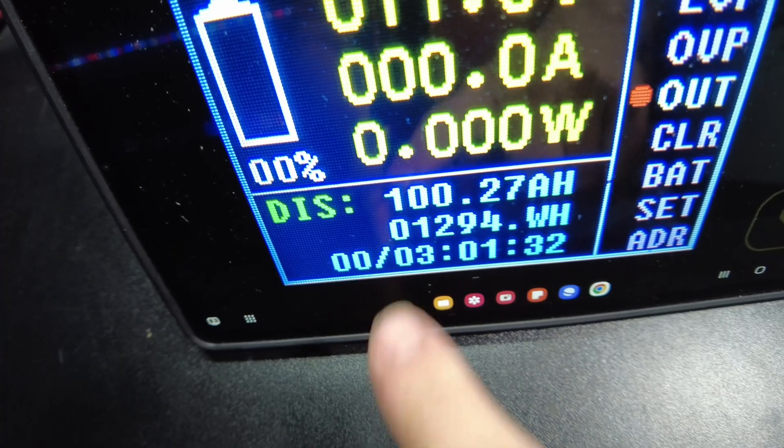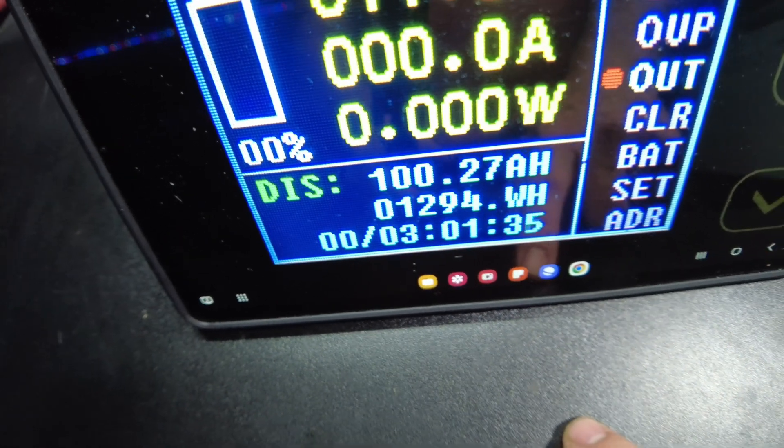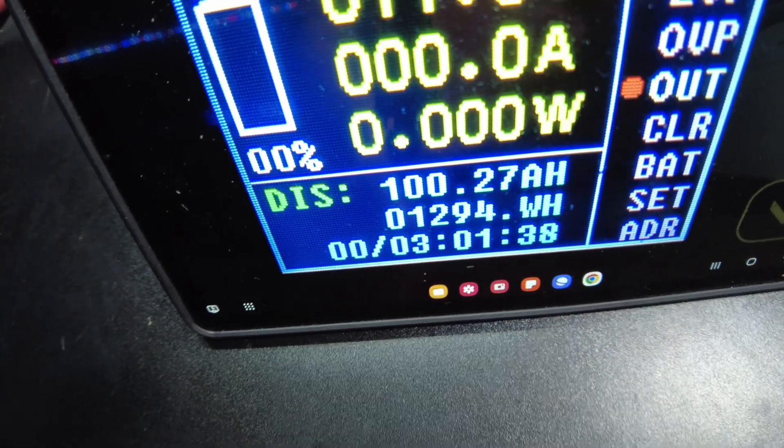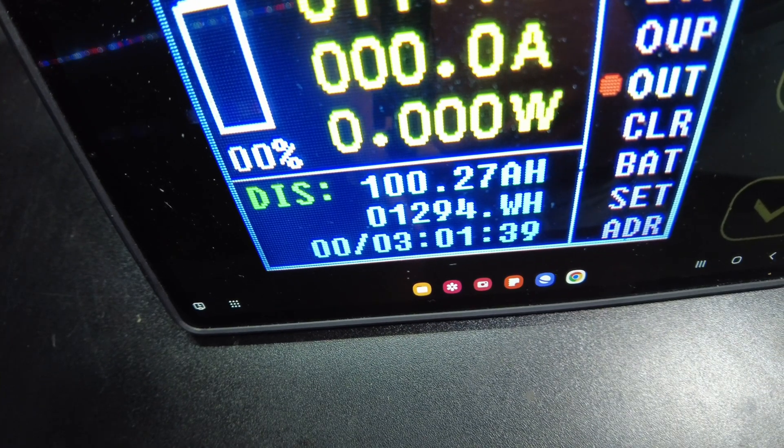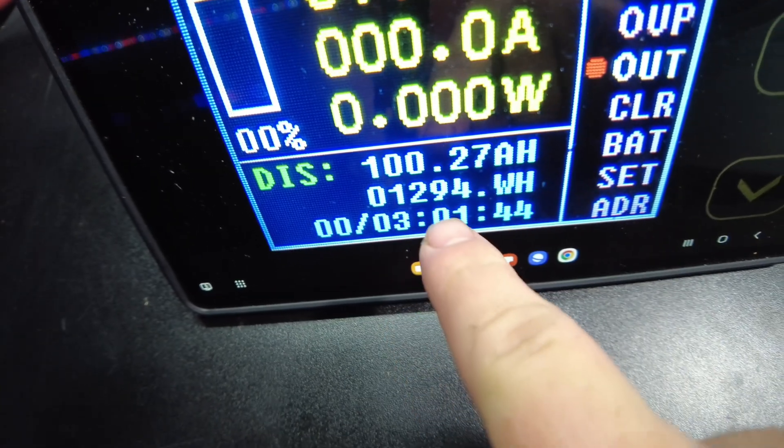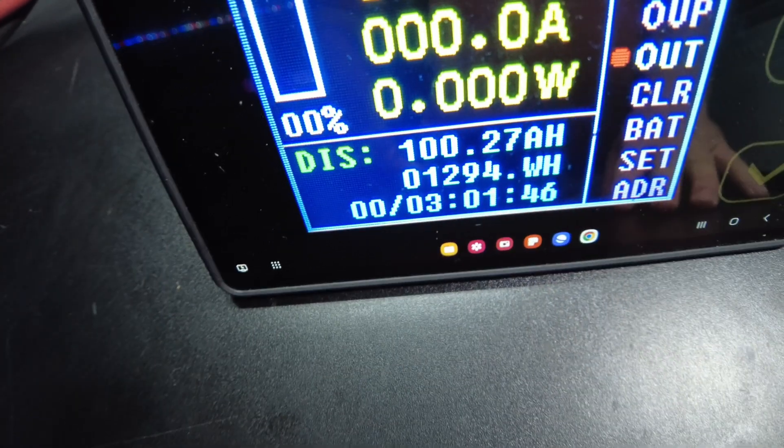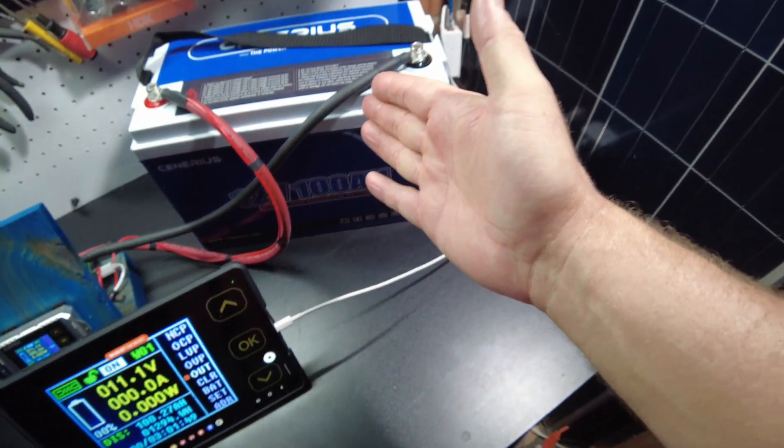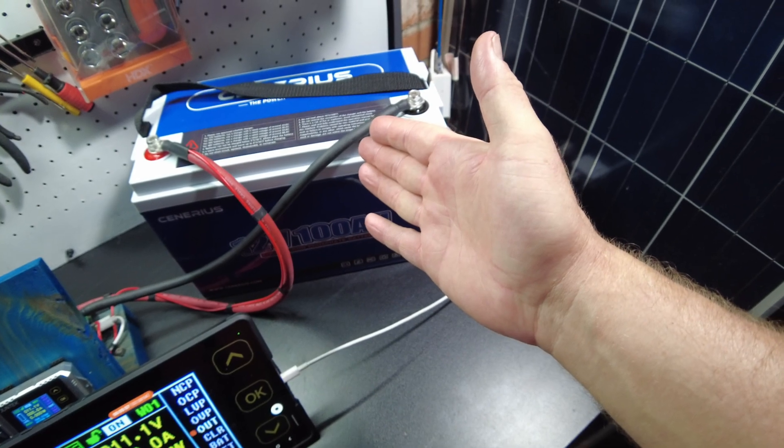So, that was close. We made it to 100.27 amp hours. 1,294 watt hours. So, we exceeded the amp hours and we did exceed the watt hours. We do pass the capacity test for this battery. Fantastic.